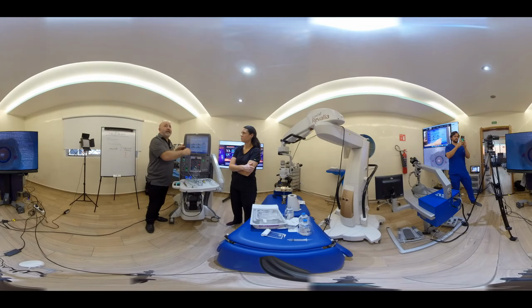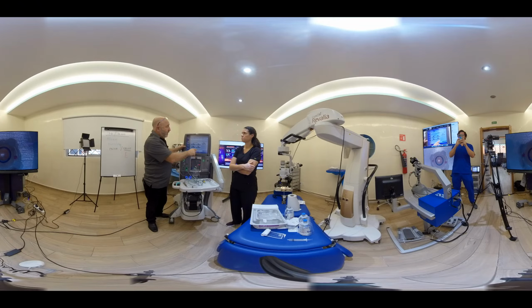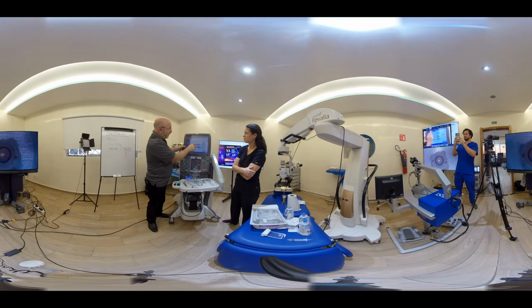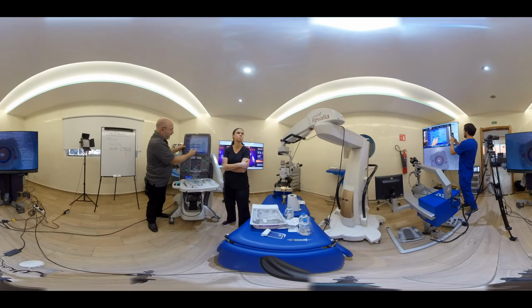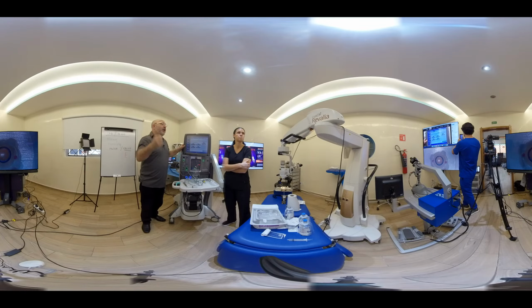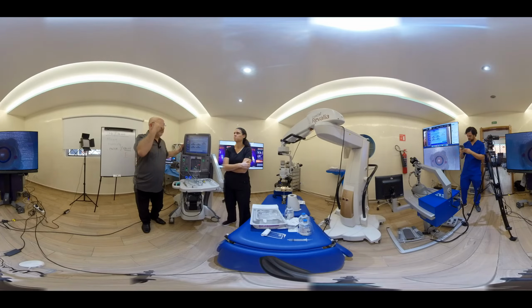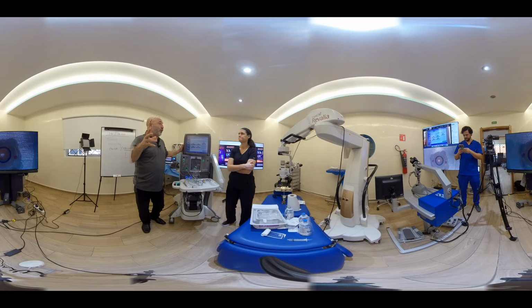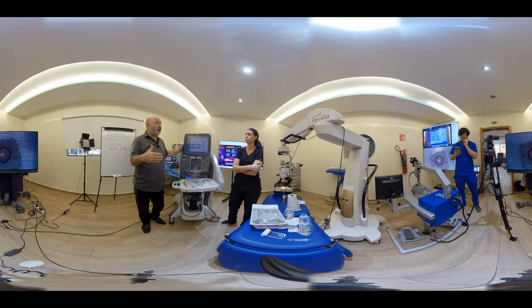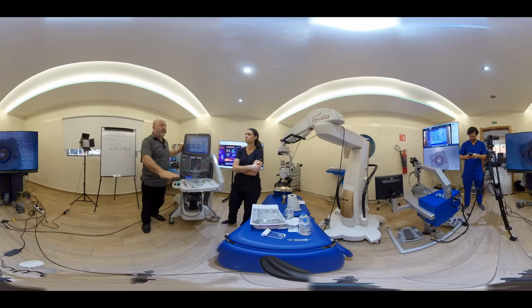This says, hang on a minute. When you trigger a threshold of say 6 cc's a minute for 23 gauge or 27 gauge, you set these independently. Stop pushing, stop chasing that pressure. So the fountain then doesn't grow. And you can play around with different numbers. I've done 0 through to bigger numbers. I kind of like low numbers. But again, this is only active if your foot's off the pedal.